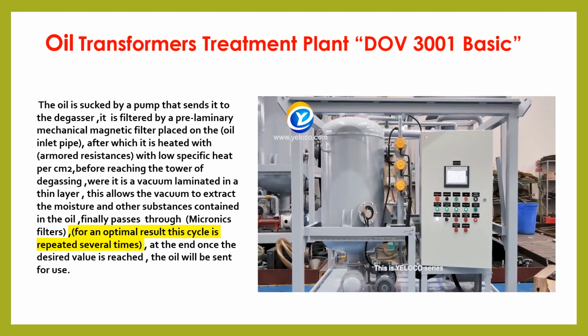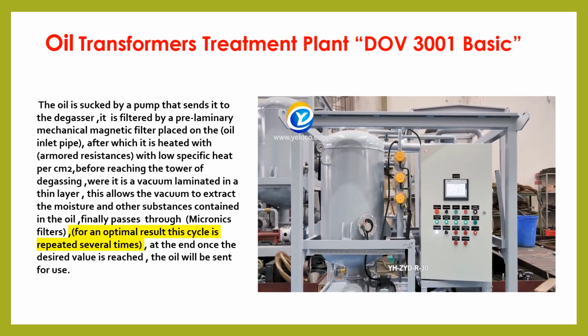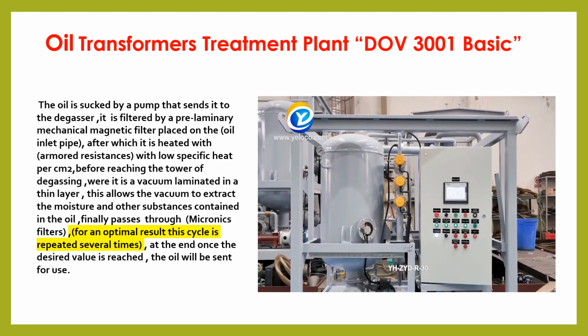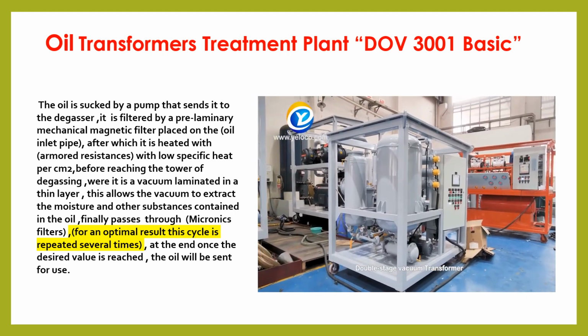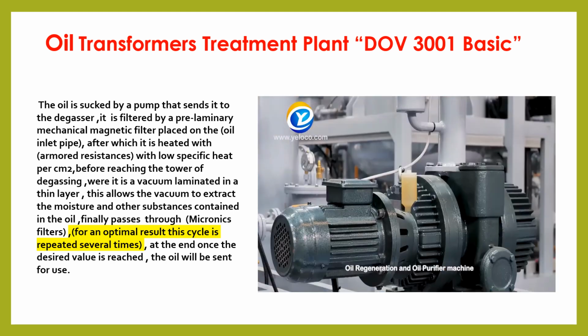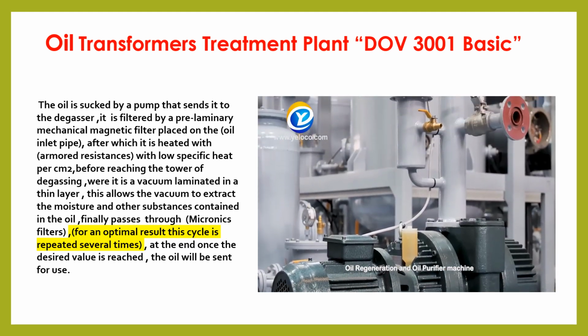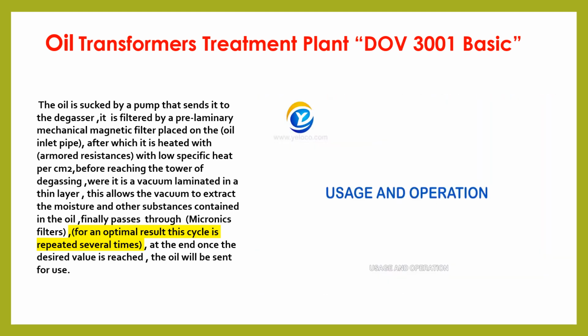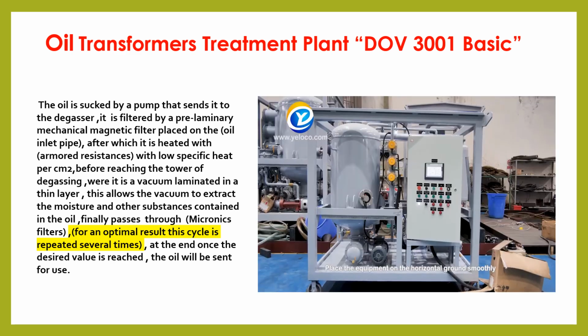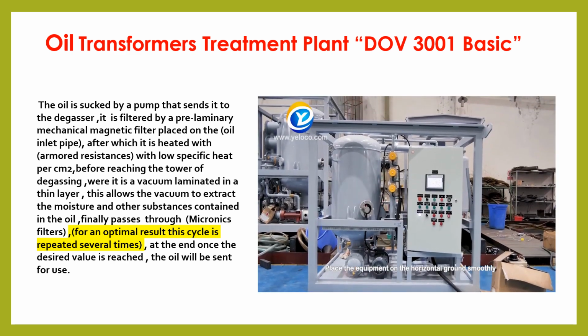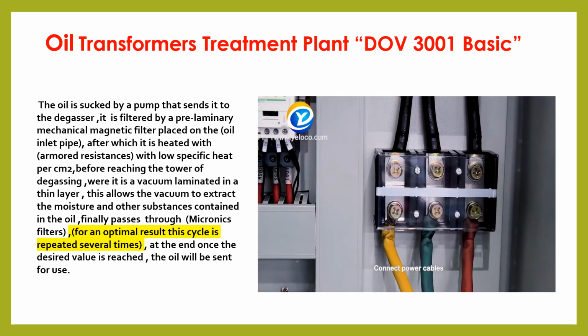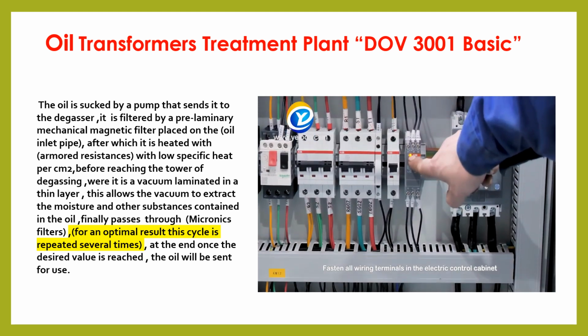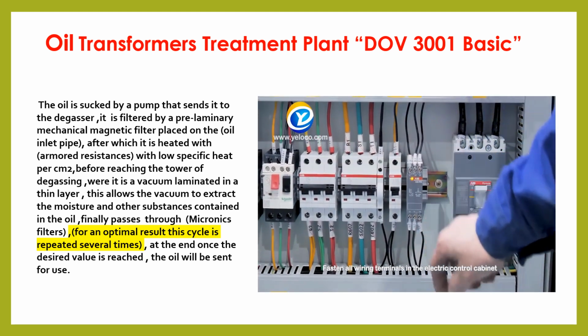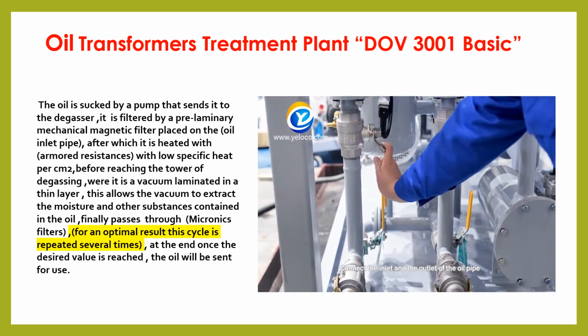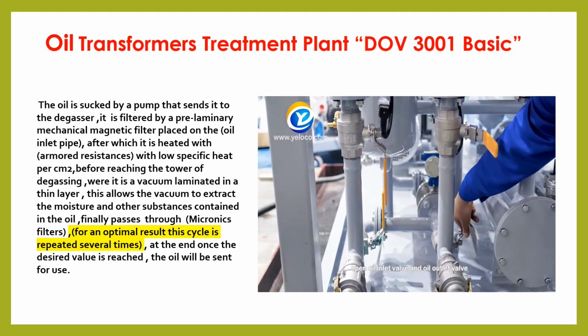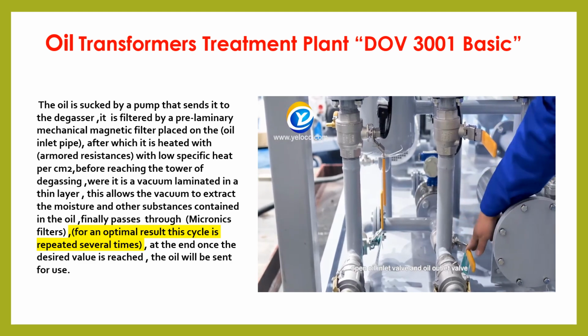This is the Yeloco Series YH-ZYD R30, 1800 liters per hour, double-stage vacuum transformer oil regeneration and oil purifier machine. Usage and operation. Place the equipment on horizontal ground smoothly. Connect power cables. Fasten all wiring terminals in the electric control cabinet. Connect the inlet and the outlet of the oil pipe. Open oil inlet valve and oil outlet valve.